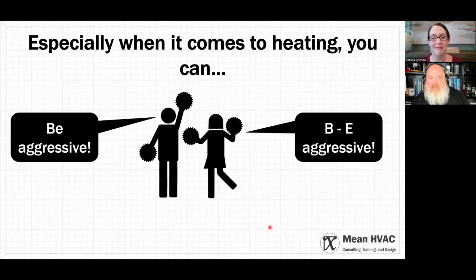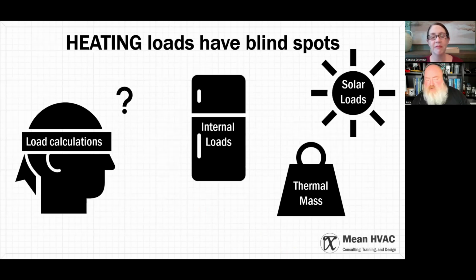Be aggressive when you're sizing a heat pump. When it comes to heating, go ahead and make it smaller, because heating loads, when you do the calculations, are very worst-case. Manual J doesn't look at internal loads in the wintertime, doesn't look at the thermal mass of the home holding onto heat, and doesn't look at the sun heating up your home in winter. So generally speaking, heating systems tend to outperform the load calculation by a pretty good margin.